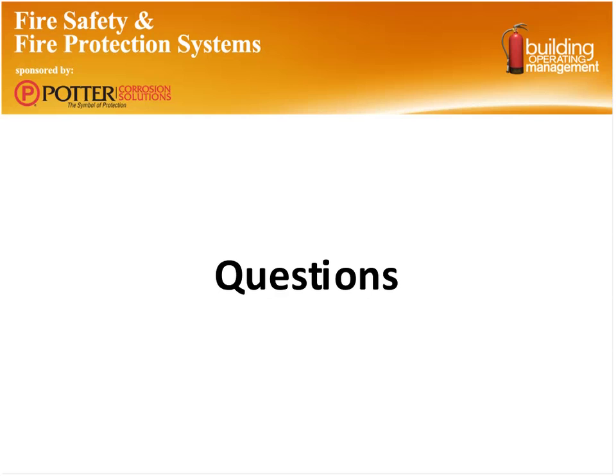Okay, here's a question about what methods can you use to protect your pipes if you have a wet system that is integrated with a perimeter HVAC heat pump system? That's an interesting one. I guess I haven't run into one of those kind of systems, so that would be interesting. You could probably still use some nitrogen injection within the water. There are systems that can, as long as it's not a water that's being continually made up, otherwise more and more water being put into the system. Otherwise, it wouldn't work with a combination potable water, fire sprinkler water system, because you'd be changing out your water faster than that nitrogen system could make up or reduce the oxygen content within that wet pipe. So just not real familiar with that type of combined system.